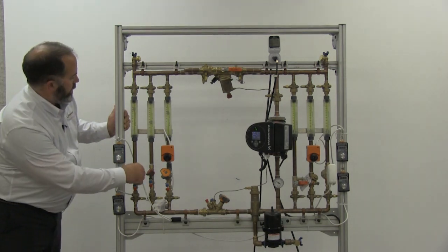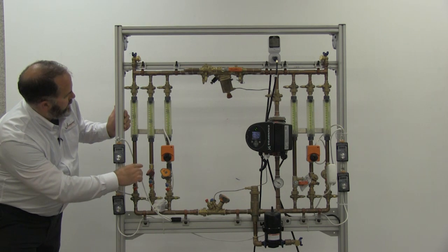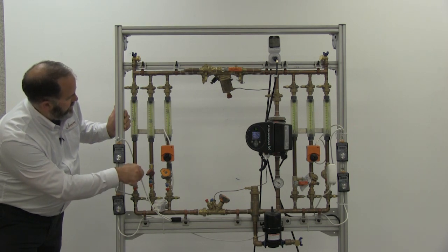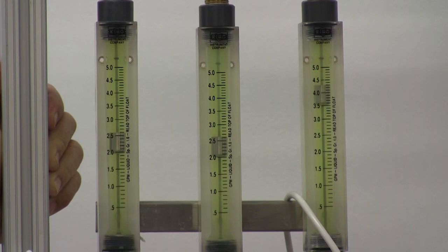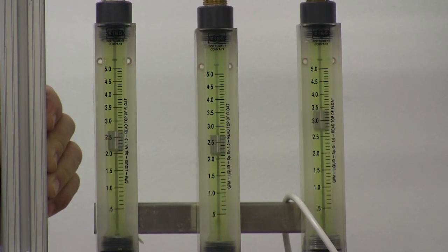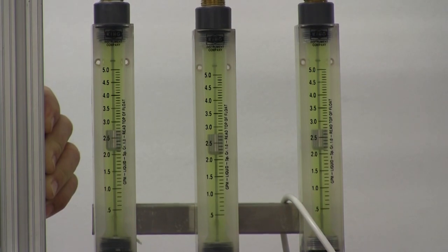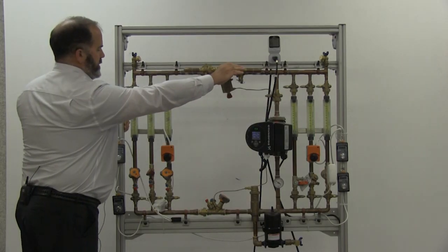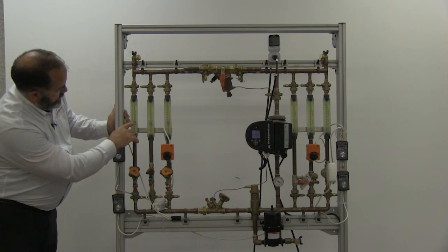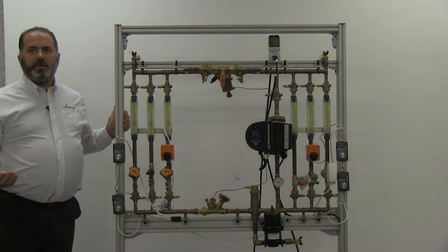So again, I'll start with proportional balancing, bringing everything to the same amount of overflow. And then we'll now activate our differential pressure controller. And that'll bring us to our design flow rate of 2 GPM.